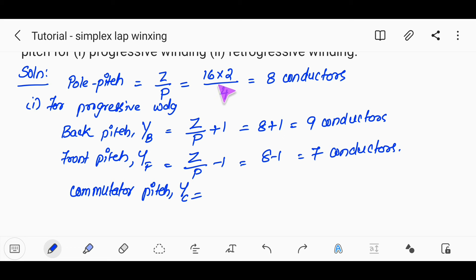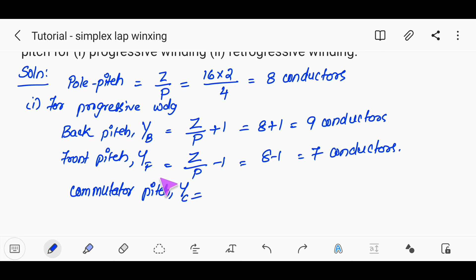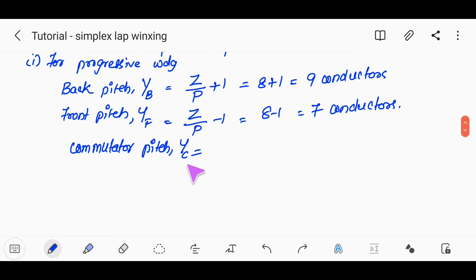Number of coils equals number of slots multiplied by number of conductors per slot, which is 16 multiplied by 2 divided by 2, giving 16 coils. For progressive winding: back pitch Yb equals Z divided by P plus 1, that is 8 plus 1 equals 9 conductors. Front pitch Yf equals Z divided by P minus 1, that is 8 minus 1 equals 7 conductors.